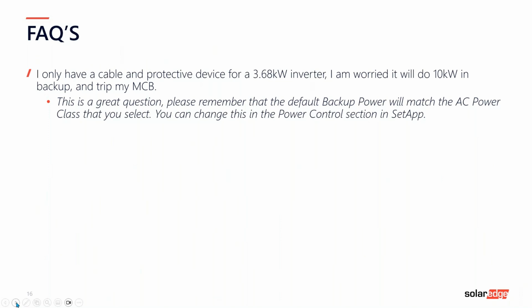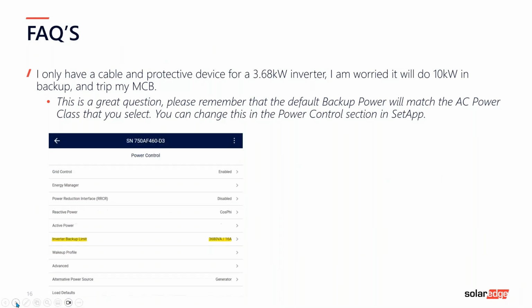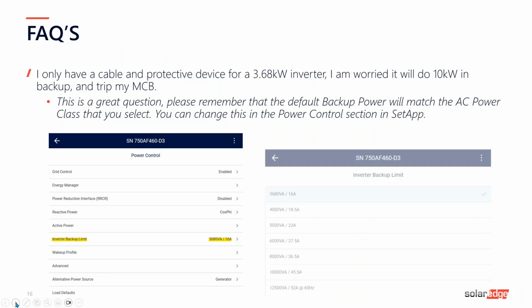Please remember the default backup power will match the AC power that you select. You can change this in the Power Control section in SetApp. I said it was a default value, but if you've wired it with a big enough circuit breaker and big enough cable, you can make the inverter do any values you want in backup. The inverter backup limit you can see is highlighted here. It's a 3.68 model I installed and it's at 3.68. Let's have a look at the next slide.